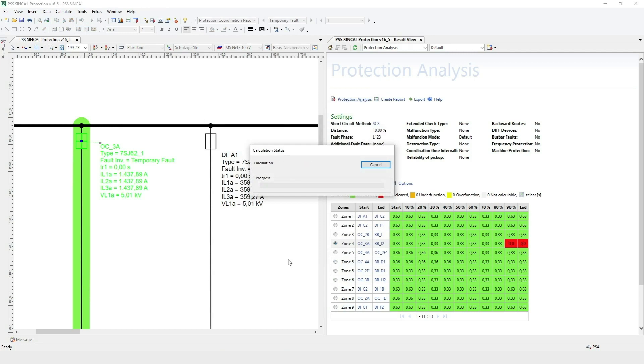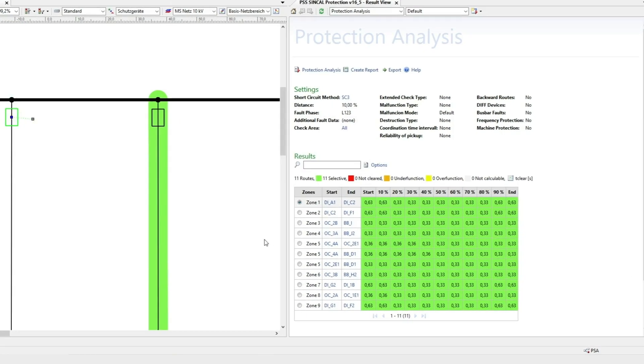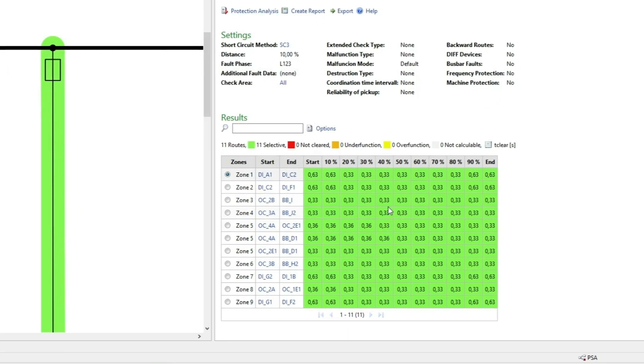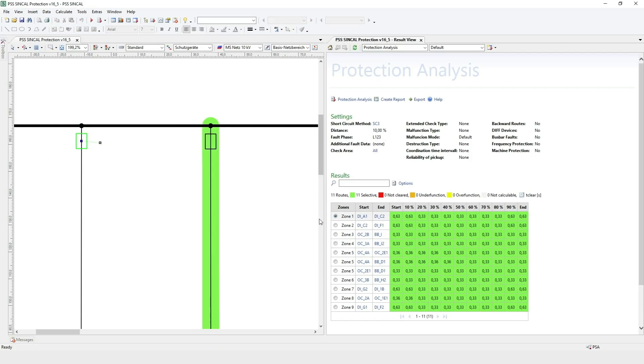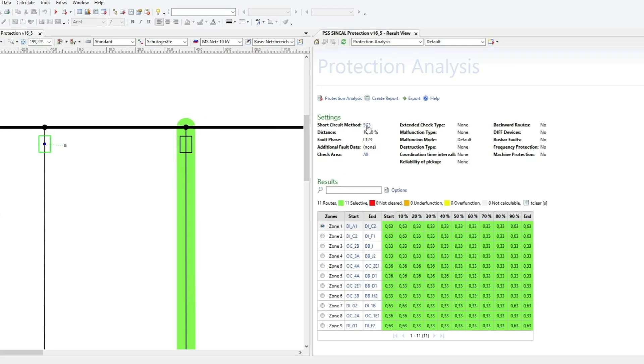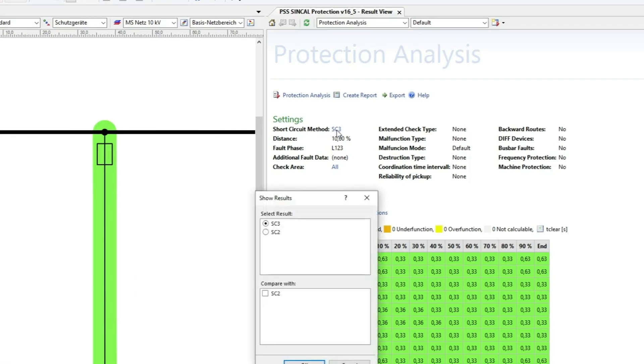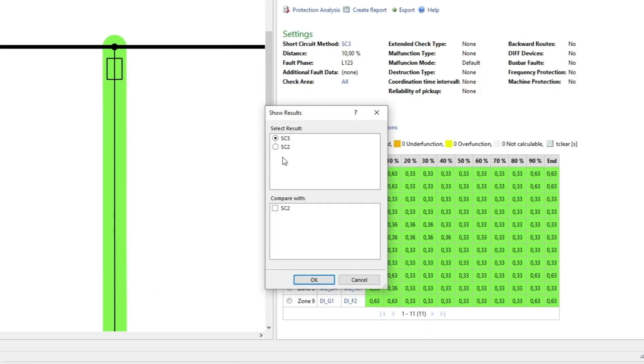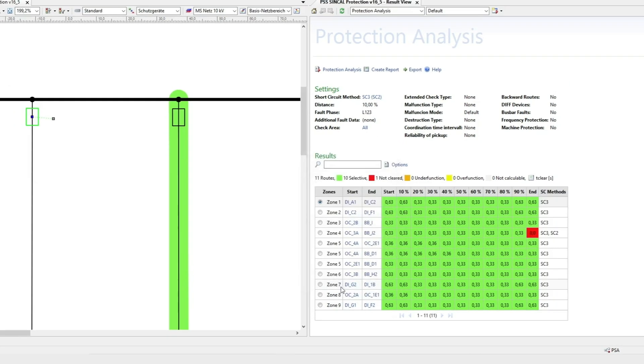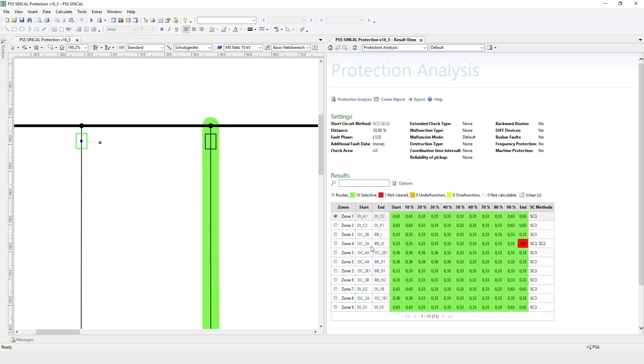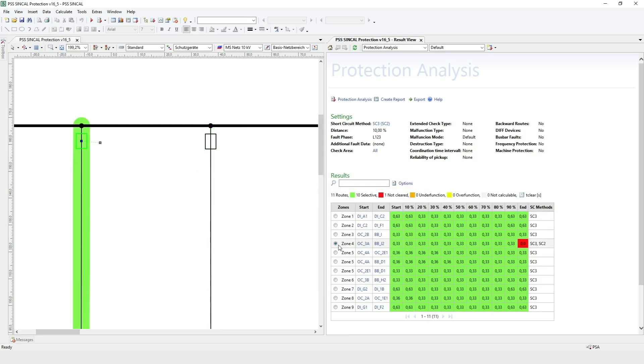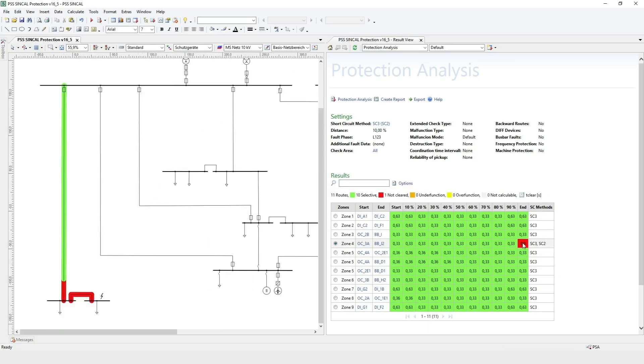Let's perform the protection analysis again. We see the not cleared fault locations disappeared. Now that we've looked at the three-phase fault results, let's check the worst-case results from all fault types. Select the short circuit method and compare the three-phase fault results with the two-phase fault results. There is still one not cleared fault location in the case of a two-phase short circuit.